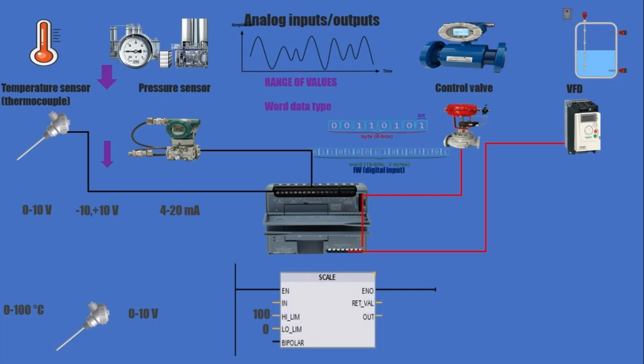Another operation the scale carries out is converting the signal received in the input or output module to machine language. Thus, four scales are available in TIA Portal: 0 to +27,648, 0 to +32,767, and their negative counterparts in case the device delivers negative signal.